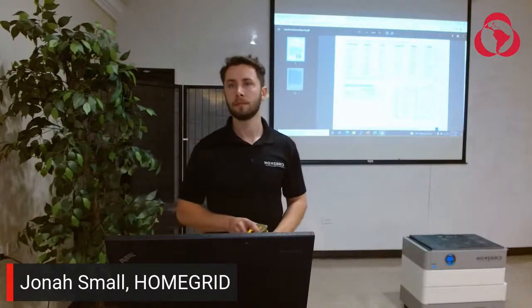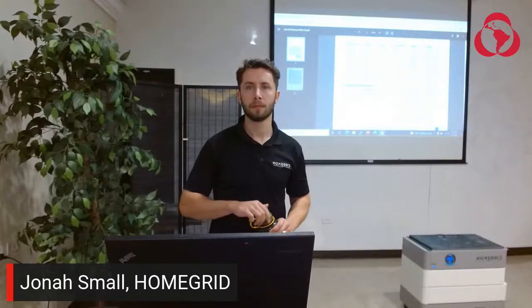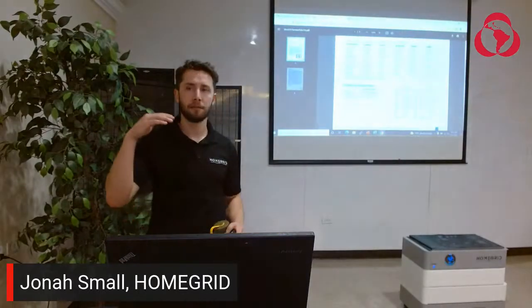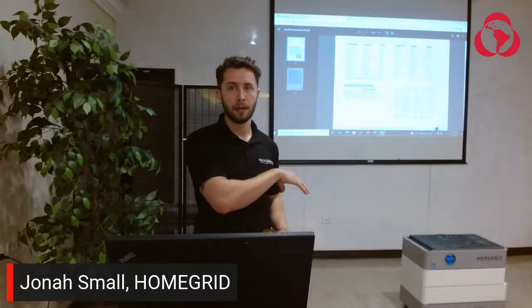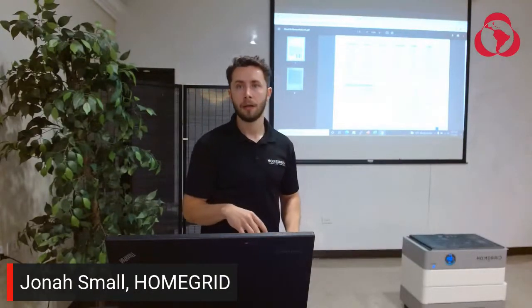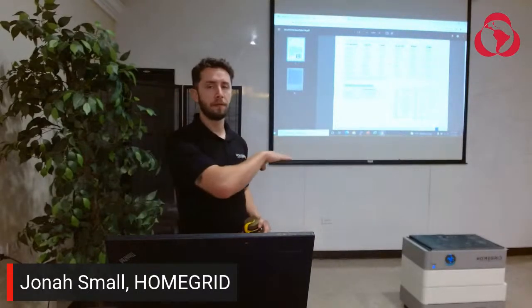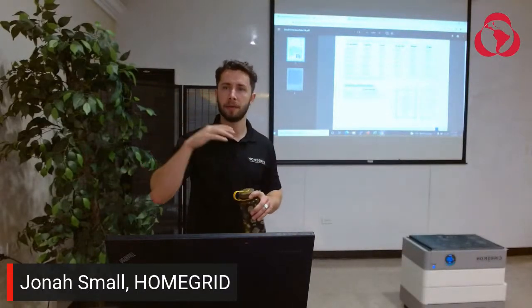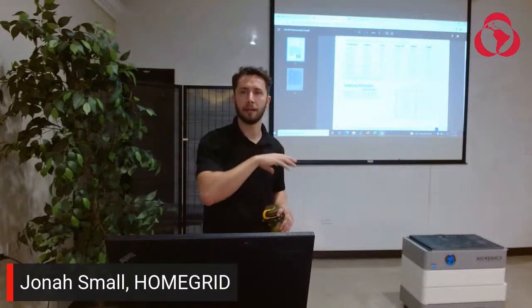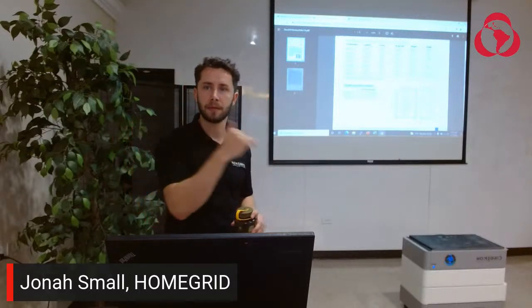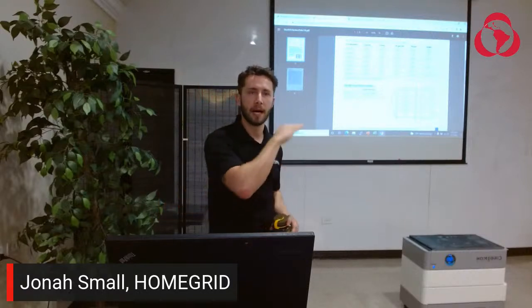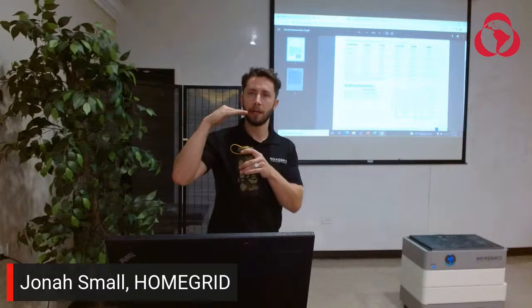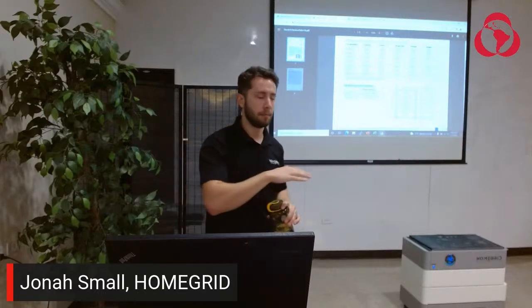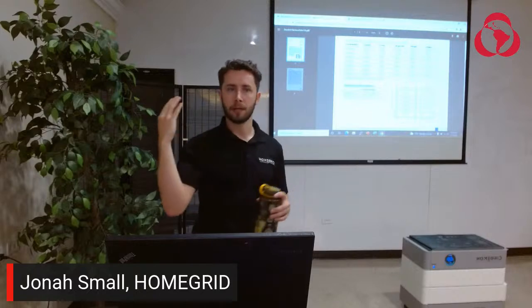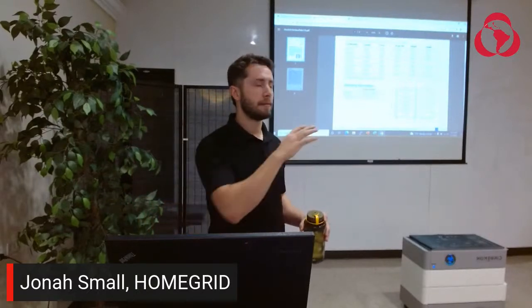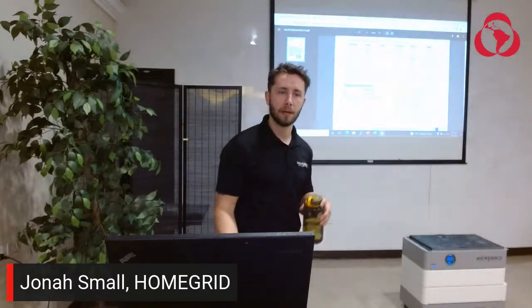What's the maximum current capacity you can feed to discharge the battery? Are you talking amps for just the battery? Yeah, if it's fully discharged and you have a massive generator or the grid. It depends because it's a 48 volt battery, so the amps change depending on configuration. From the inverter to the battery we can take up to 312 amps to charge the battery system, depending on the size. A smaller stack limits it to around 200 amps, but the largest we can do at the 4 stack is 312.5 amps at 48 volts. It depends on where you're looking in the system for that current.